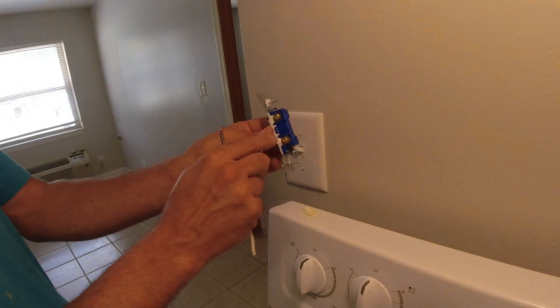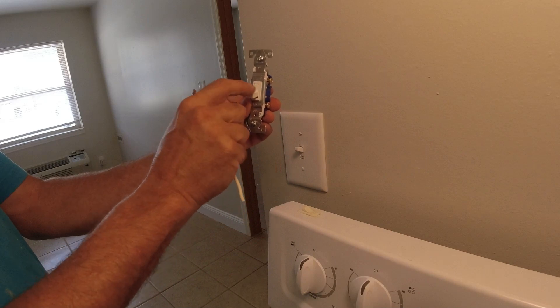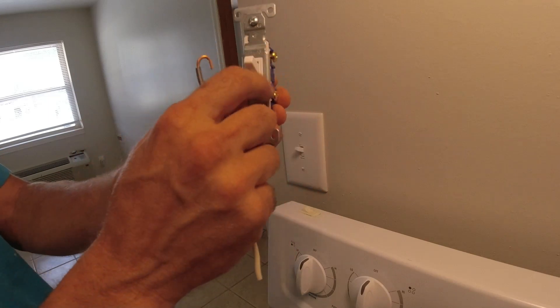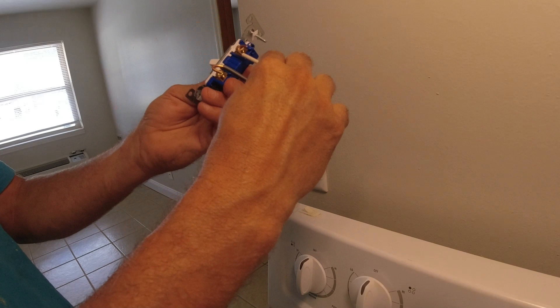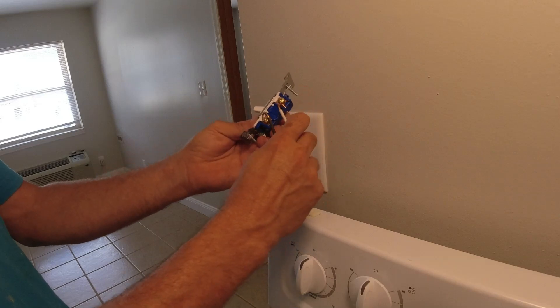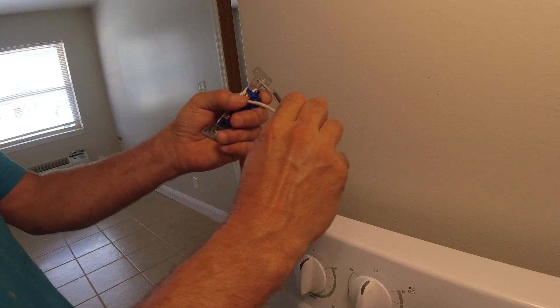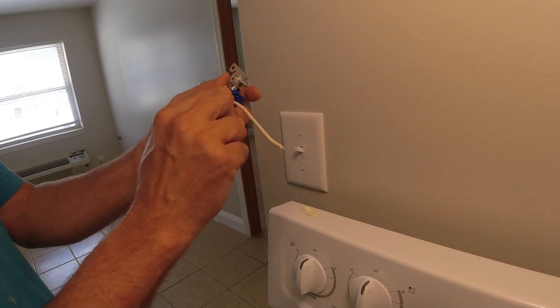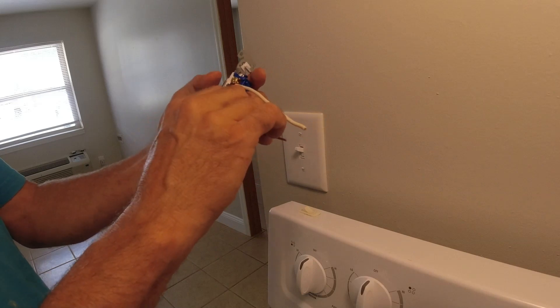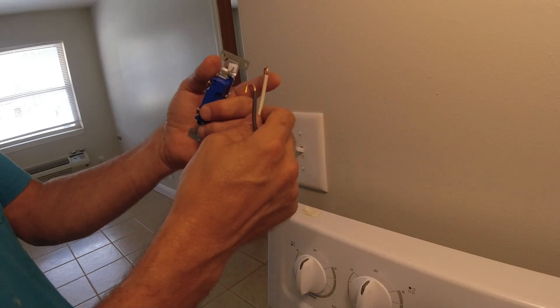For standard single pole switches — the ones with only two wires and a ground — orient the switch so that ON is up and OFF is at the bottom. These two wires don't matter which way you put them; you don't need to remember which was on top or bottom — it'll work either way. You may see two black wires, or a black and a white wire. Sometimes they'll tape the white wire to indicate it's been used as a switch leg. A lot of times they don't, so don't get confused — the white is just part of the switch leg on that circuit.